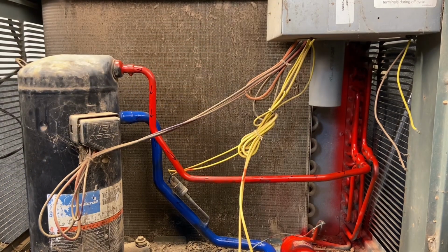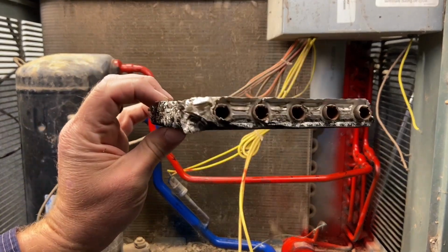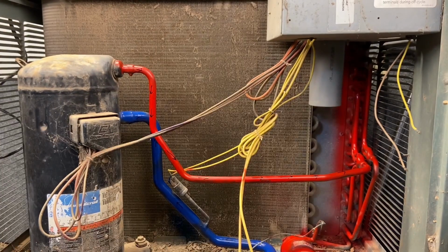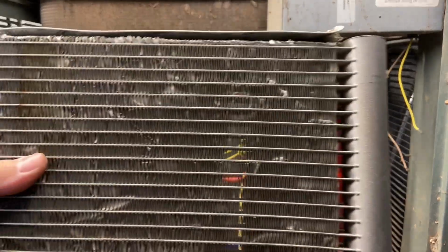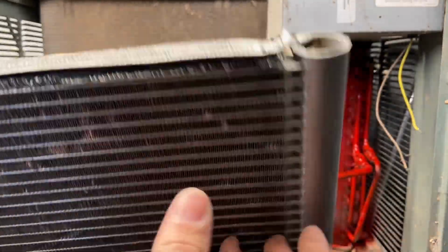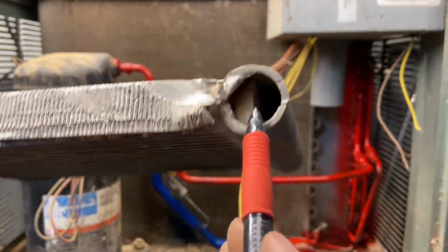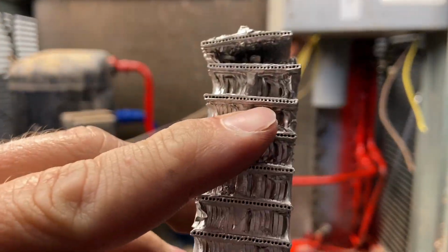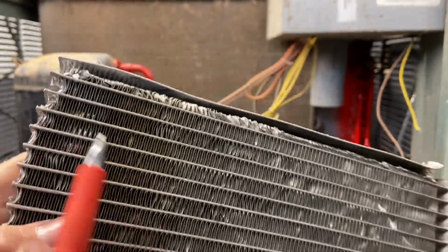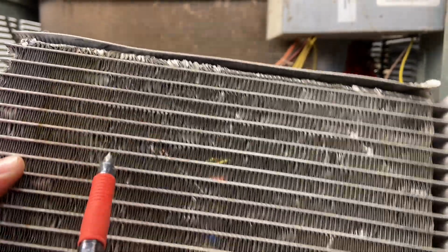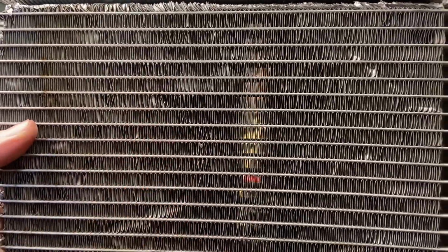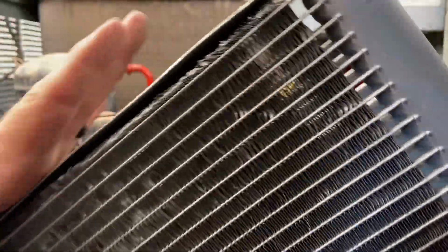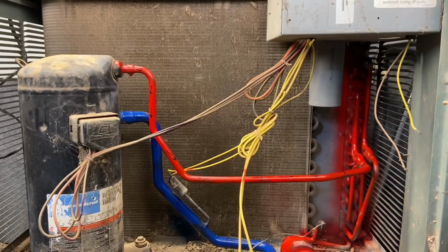Now there's many kinds. We talked about this is what we call a tube and fin. Refrigerant runs through the tubes, exchanges heat to the fins. We also have what we call a micro channel, which is similar to a radiator of a car, where we have a large chamber that the refrigerant runs through, and then it runs these little micro channels right here, these little bitty holes all of them run through, and it exchanges the heat to the aluminum. And then we're still pulling air through this, so we're exchanging the heat from the refrigerant through the metal to the air. Second law of thermodynamics still applies, different way of doing it.